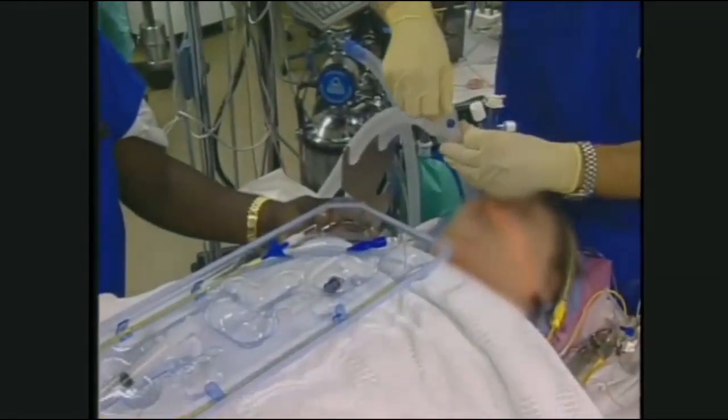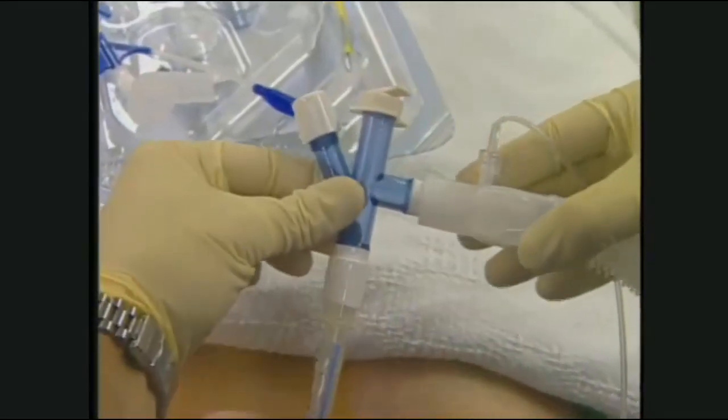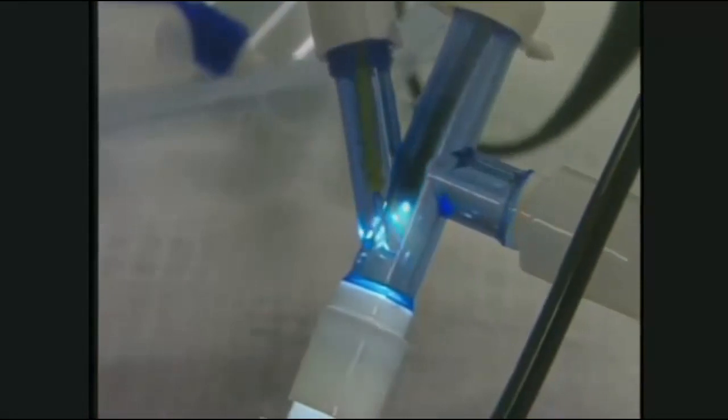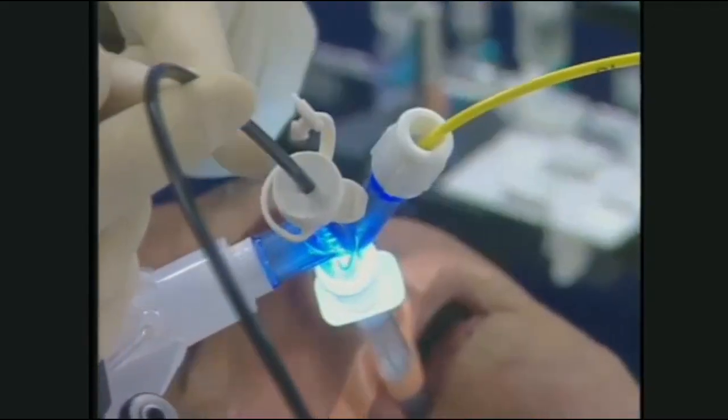The Arndt endobronchial blocker is intended for endobronchial blockade of the left or right lung for procedures which require one lung ventilation. One lung ventilation is commonly required for surgical procedures and is normally achieved using a double lumen endotracheal tube. One of the advantages of using this blocker set is that it can be used with a conventional endotracheal tube. The 3 millimeter diameter does not significantly compromise the cross-sectional area of the endotracheal tube, such that there is no noticeable change in resistance to airflow through that endotracheal tube.